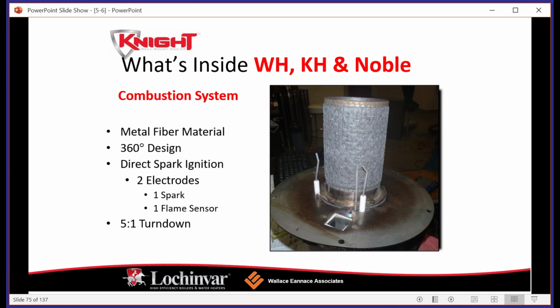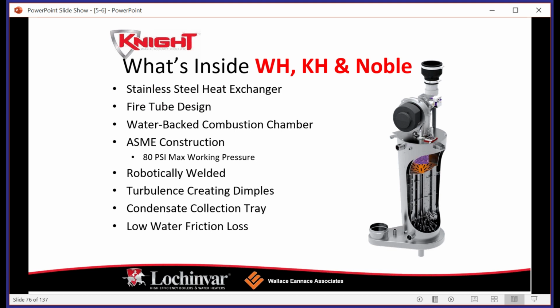But again, the metallic fiber burner is going to allow the boiler to get us to where we need to be with our BTU inputs and not create smog. The metallic fiber material may look a little different across different products, but you're not going to have any of the condensing boilers with just a direct impingement flame. It's always going to have one variation or another of the metallic fibers. And that's across water heaters, that's across boilers, the whole product line. Okay, so here's a stainless steel heat exchanger, fire tube designed.